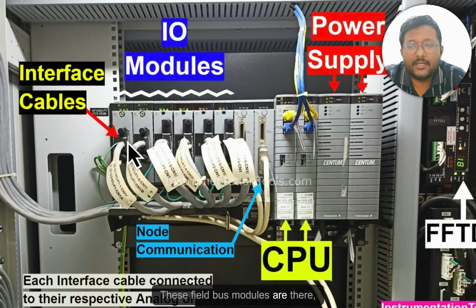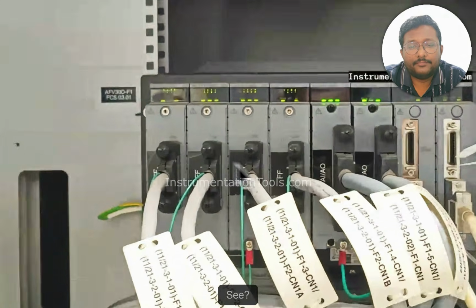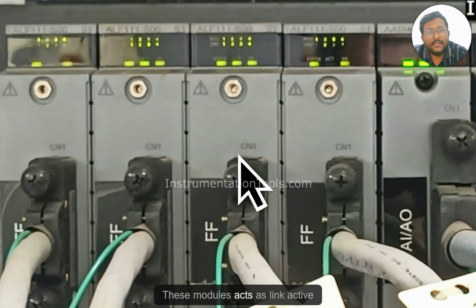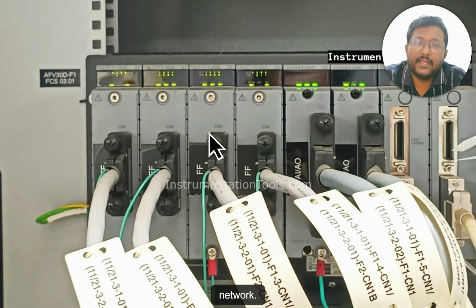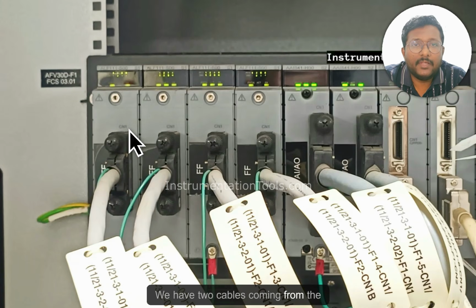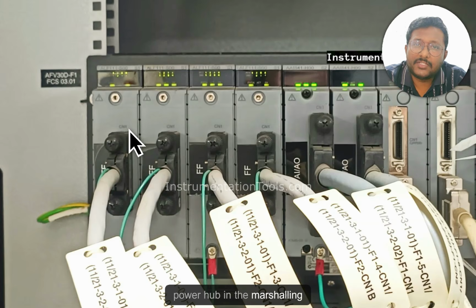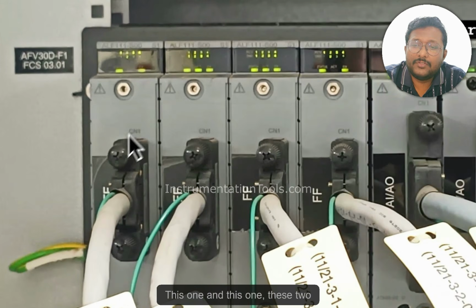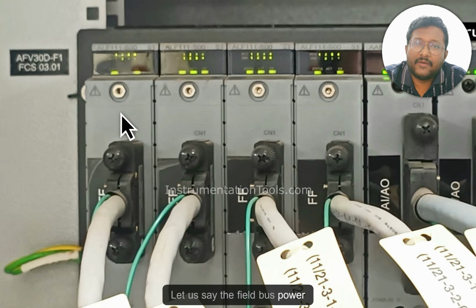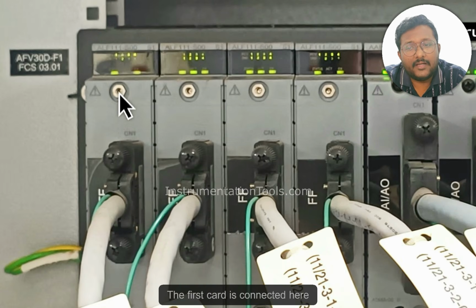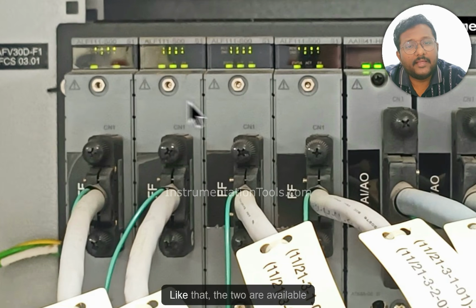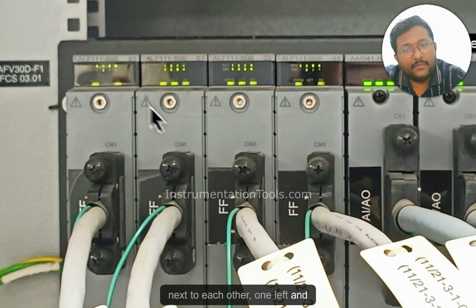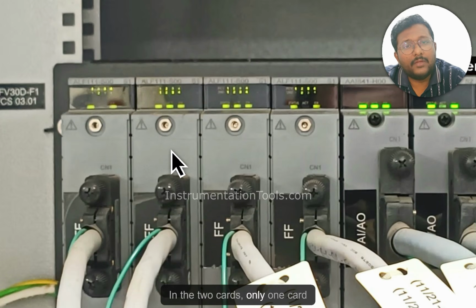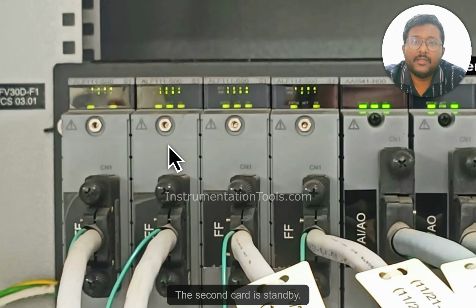These fieldbus modules are there, right? See, these modules act as link active scheduler in our network. We have two cables coming from the fieldbus power hub in the marshalling cabinet, right? In that case, let's say these two are one set. This one and this one, these two are one set. Let us say the fieldbus power hub has two cards. The first card is connected here. The second card is connected here. Like that, the two are available next to each other, one left and one right. Of the two cards, only one card will be active. The second card is standby.